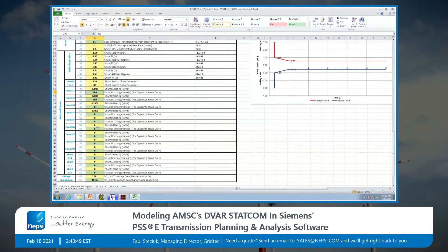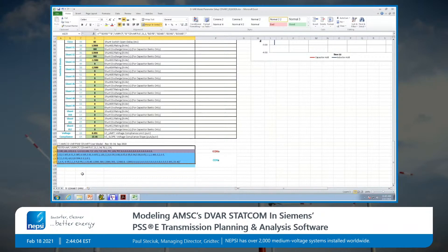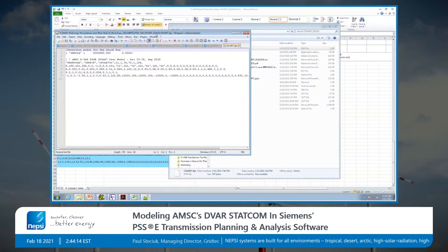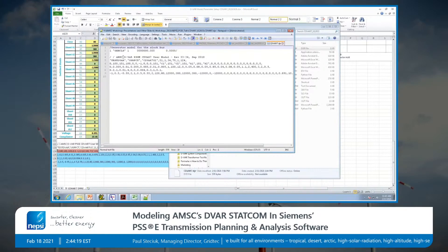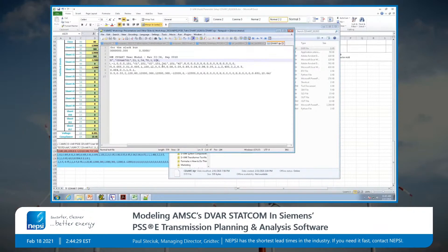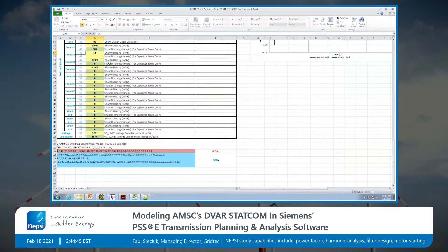The neat thing about this spreadsheet is that at the very end, using these parameters, it automatically generates the parameters that go into the DYR file — the dynamic data file. Opening that file, which is needed for PSSE transient stability simulation, you can see we have a generator model for the slack bus and then the STATCOM model. All the parameters shown in the spreadsheet are turned into this text format. Instead of trying to figure out which number to change directly in the DYR file, it's easier to come into the spreadsheet, make a change — like changing the size of your capacitor — and it automatically updates and you can copy-paste the whole thing into the DYR file.